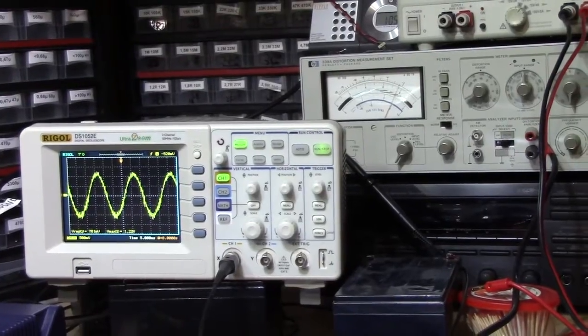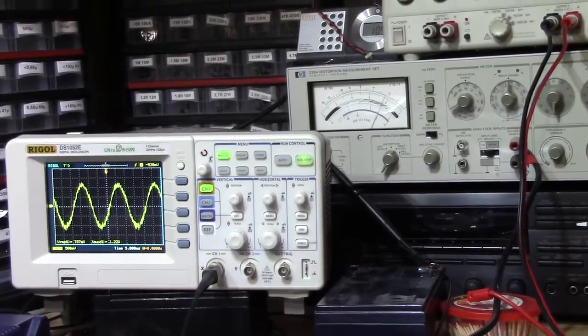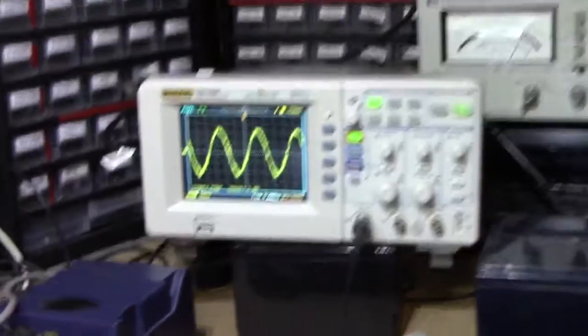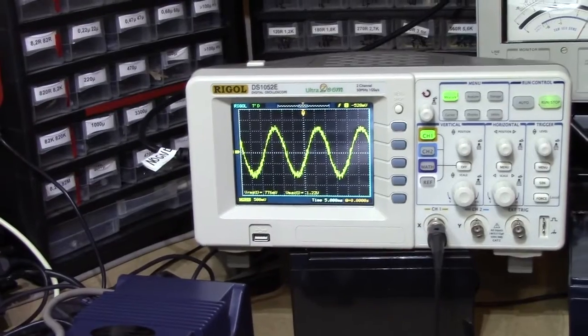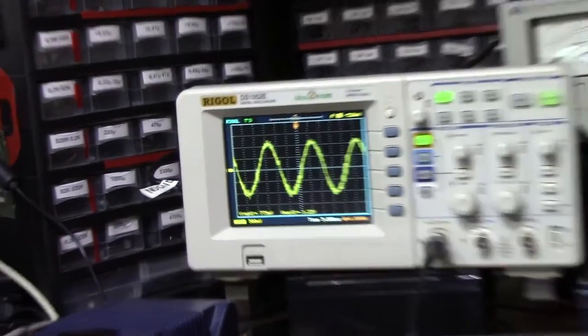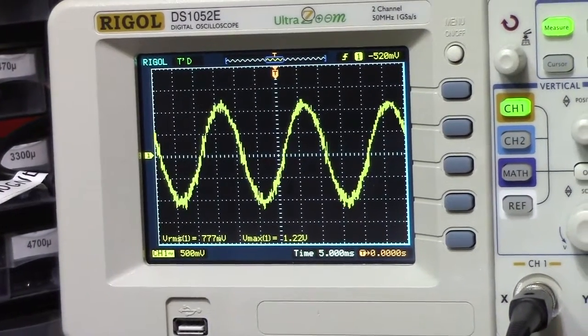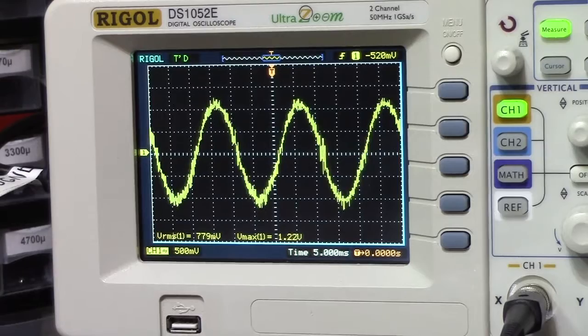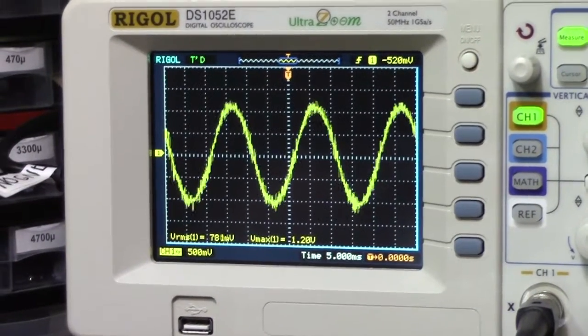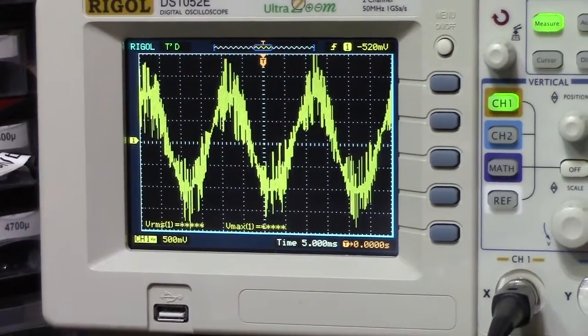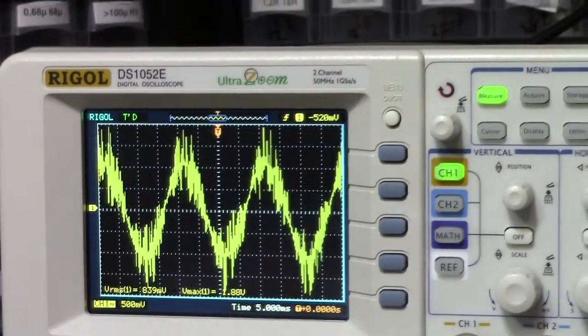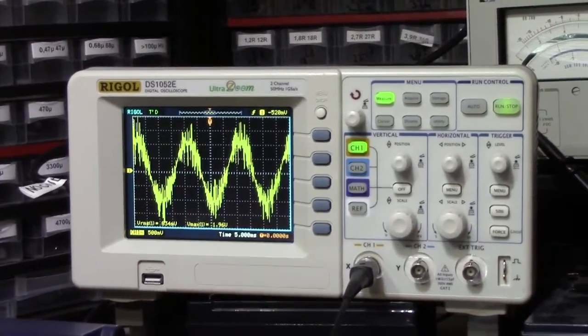Check this out. We're now hooked up through the distortion analyzer, with the Rigol scope hooked up to the monitor output, and also using the ungrounded power lead that my analog scope normally uses. And we can already, without any load on the UPS, see that our output waveform is very, very ugly. Now, look what happens when I turn the load on. That looks absolutely horrible.